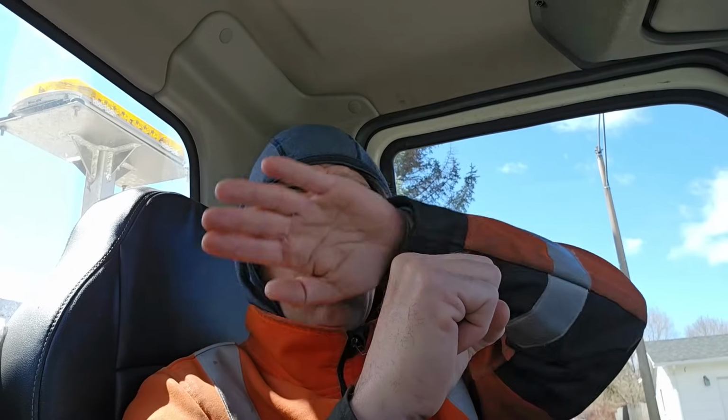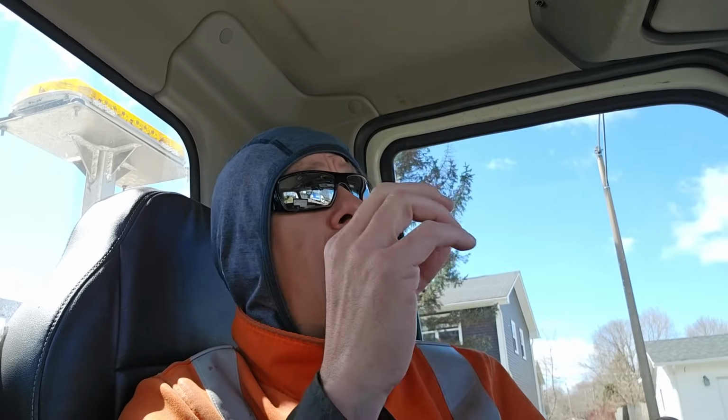So what I usually do when I take a work permit, I check all protection points myself. I look at the work area, and around my isolation zone, any switch that has an alternate feed coming in, there's a switch supposed to be open. I verify those all on my own on the computer. If I see an issue, then I will speak to my dispatcher, and he may say, no, that switch in the field's actually closed because there's a breaker out or whatever. I like to do that on my own without any outside influence. I find it better verifies your work.